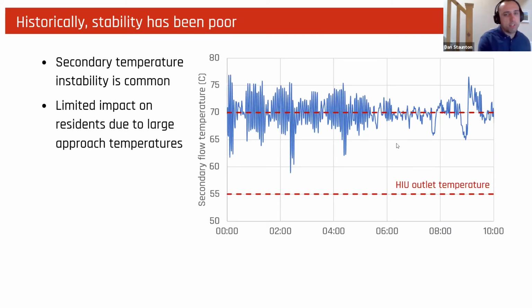Historically, though, outlet temperature stability from plate heat exchangers has been poor. So the data on the right-hand side here shows the secondary flow temperature off a plate heat exchanger, taken just a couple of weeks ago from the site. During periods of low demand, so before around 5 o'clock in the morning, we're getting really quite unstable temperatures. The target outlet is 70 degrees, but it's varying between 75 and 60 degrees. As demand starts to increase, past 6 o'clock onwards, we start to see slightly more stable operation, but still fluctuating between 75 and 65 degrees.